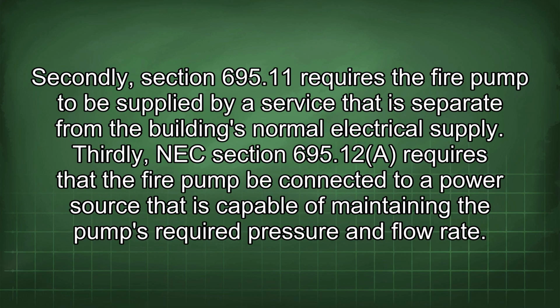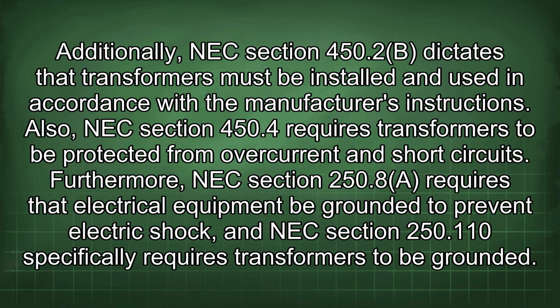Secondly, Section 695.11 requires a fire pump to be supplied by a service that is separate from the building's normal electrical supply. Thirdly, NEC Section 695.12 requires that the fire pump be connected to a power source that is capable of maintaining the pump's required pressure and flow rate. Additionally, NEC Section 450.2b dictates that transformers must be installed and used in accordance with the manufacturer's instructions. Also, NEC Section 450.4 requires transformers to be protected from overcurrent and short circuits.